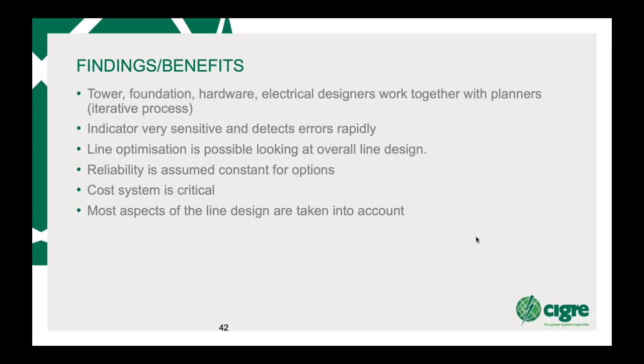So looking at the findings and benefits of using this kind of indicator, you're now not designing a line for a particular conductor, where, for example, the planners would use quad zebra R, X and B values to do the load flows. In the past, you would hand that over to the designers. They would take a quad zebra standard tower, standard design, and just build the line. However, now you're looking at a lot of optimization. So your tower, foundation, hardware, and electrical designers have to work together. Your civil engineers, mechanical engineers, electrical engineers and planners, and of course the experts in corona, insulation coordination and insulator design, have to work together with the planners to give you this particular design.